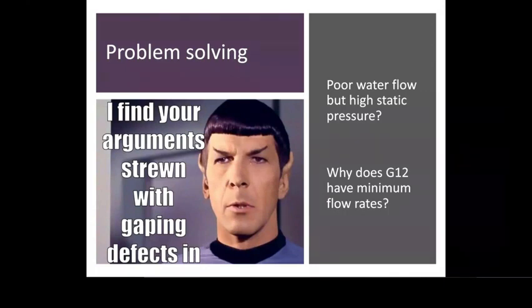Yep. So we get a few answers here. Blocked filters. Yep, that's definitely a possibility. You can get that on a pump system as well, but some people have filters, even just line strainers. So if they're blocked up with a stone, I've had that before, line strainer blocked with a stone, and the symptom was that they had a crappy shower, or the shower would go and then it wouldn't work properly. Initially they didn't even tell me it was affecting all the outlets of the tap. It was only once I got there, started mucking around with the shower, I thought it was a shower mixer issue, that I got out of them that it actually happened at other outlets, and eventually traced it back to a rock in the line strainer that happened to be in the ceiling of the garage, of all places.